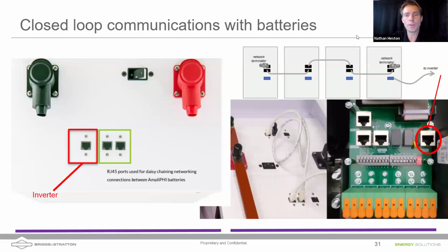If you're using our 3.8 batteries, this is showing you how to wire. This is called a daisy chain from battery 1 into battery 2, from battery 2 over to battery 3, etc. And then you would use one of the device ports on that SimpliPHI battery to go to the inverter directly from the battery to the inverter. No dongle needed for those.